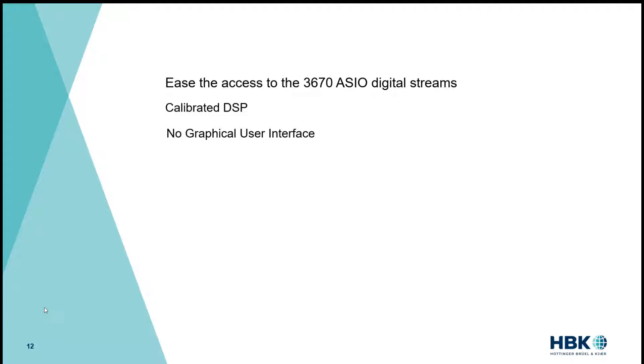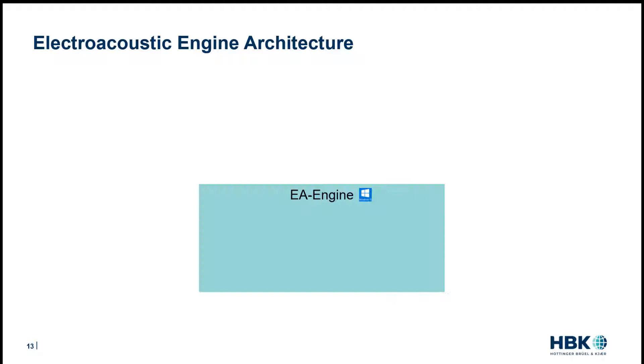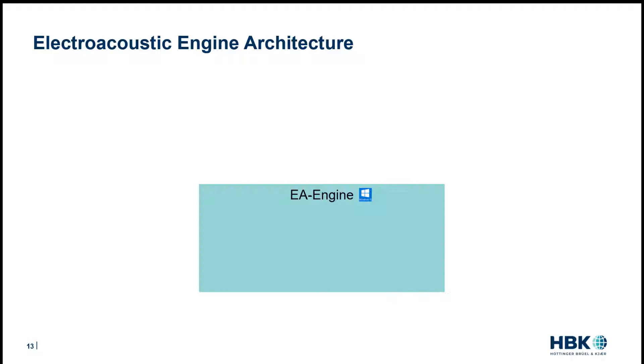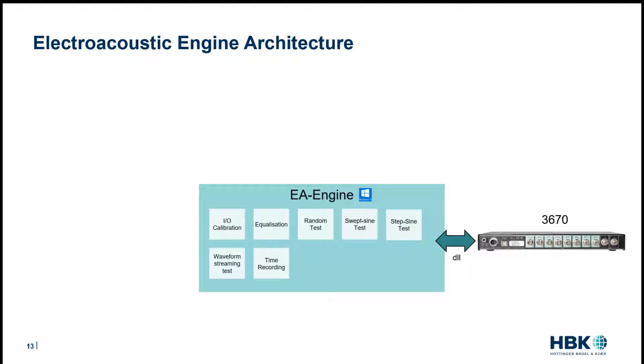The fourth principle is simple API. The HBK electroacoustic engine works on Windows, communicates with the 3670, and has different modules: I/O calibration for input or output channels, equalization, random tests, swept sine, step sine, waveform streaming to play calibrated speech or background noise, and time recording. Additionally it supports frequency analysis including spectra, phase spectrum, frequency response function, and octave-band analysis. You can also do THD and rub-and-buzz, with more features to be added.